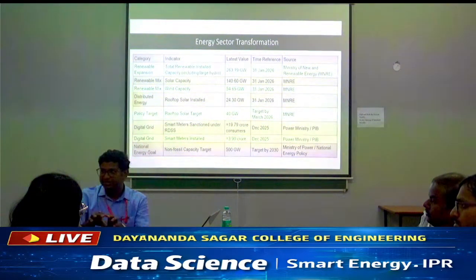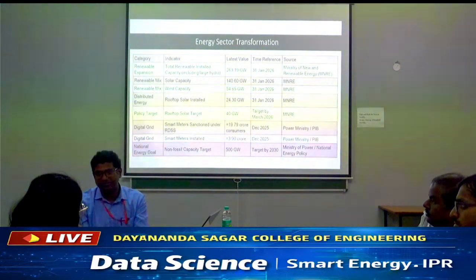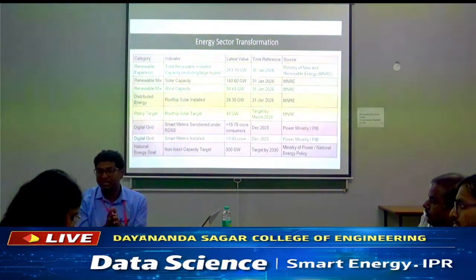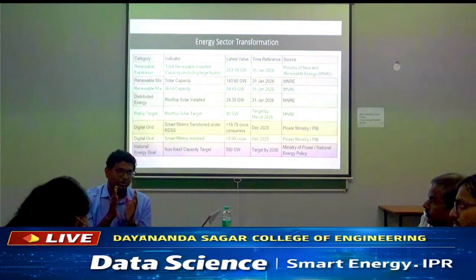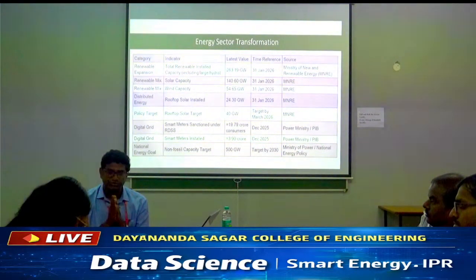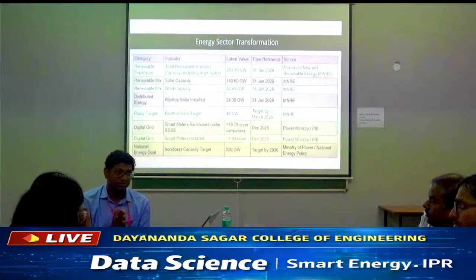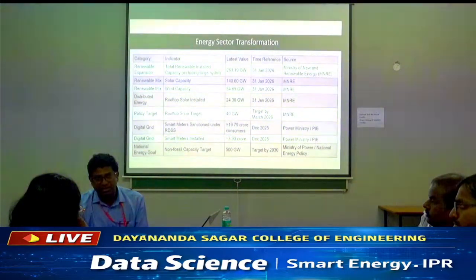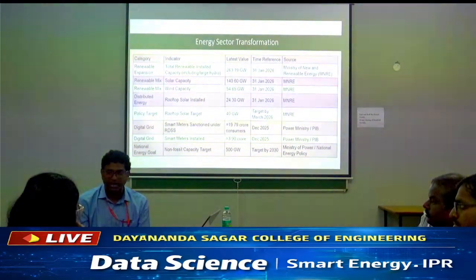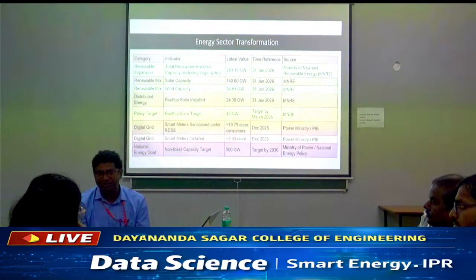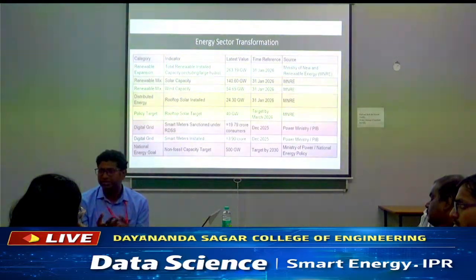Because I cannot balance all the feeders at a time. In one feeder there may be huge power, in another feeder there may be less power, or less demand. So I cannot balance it. So there is always a problem with respect to the switching station related to the power factor. If you can come up with some idea to handle this situation, then definitely you will get funding from the government, 100%. If you can come up with some logic like that, 100% you can.